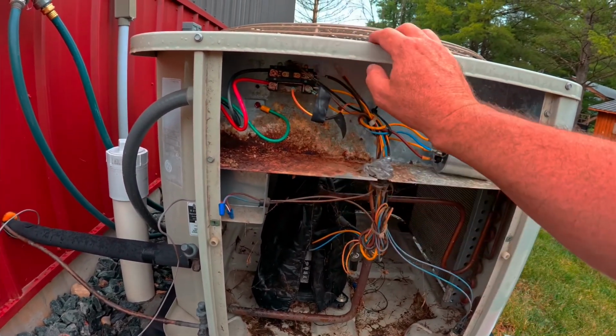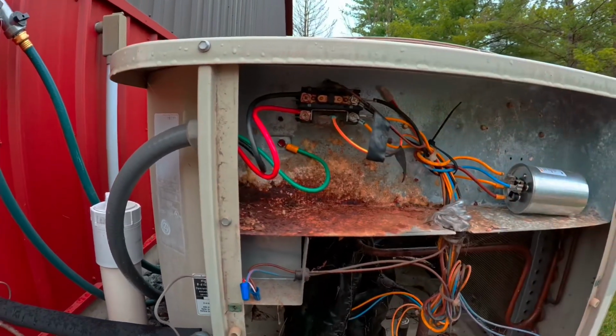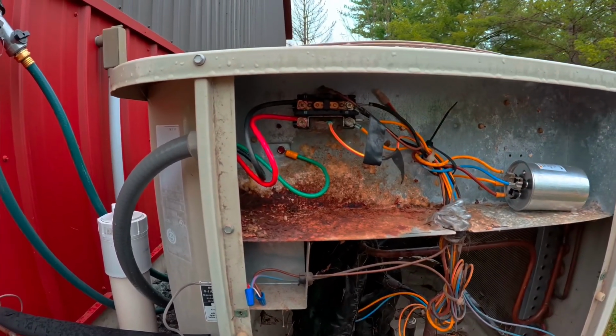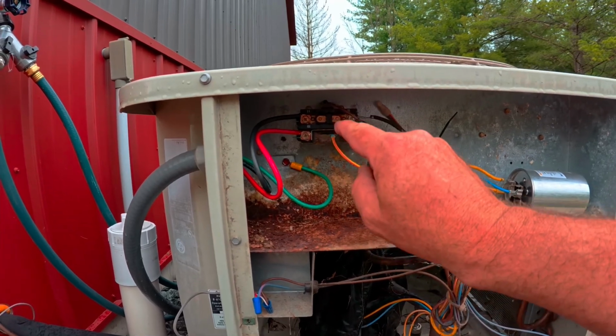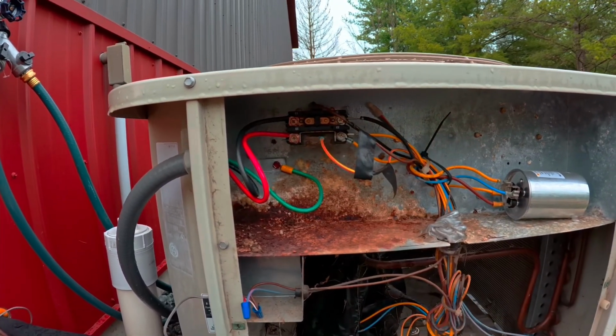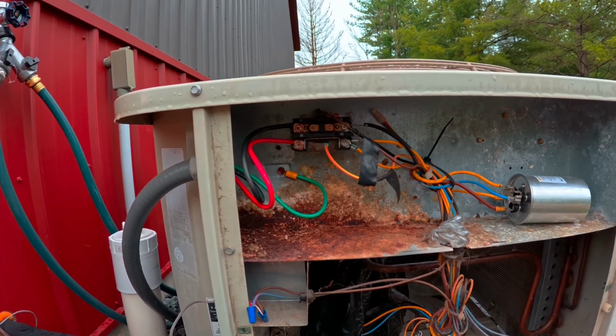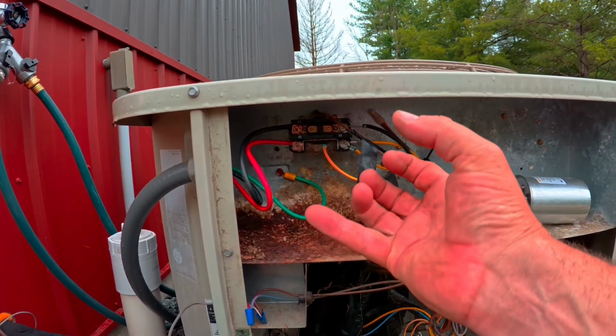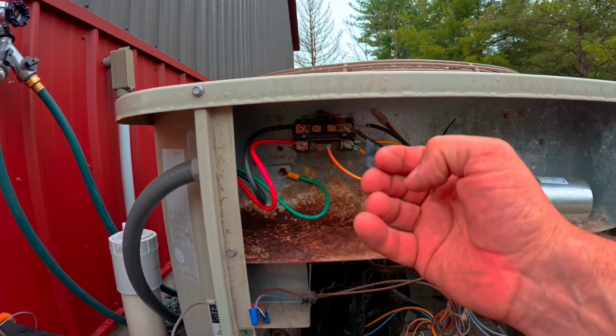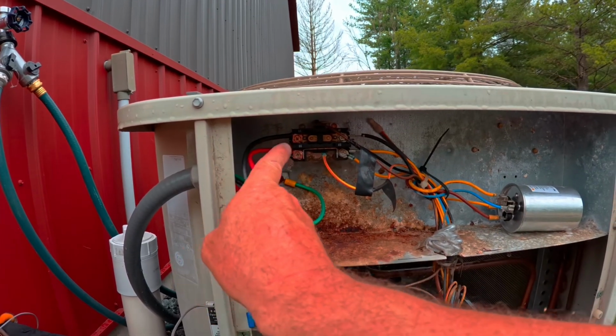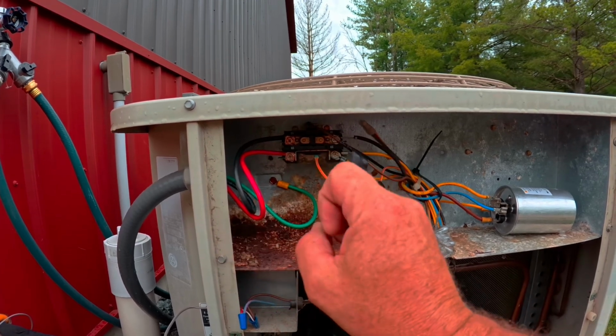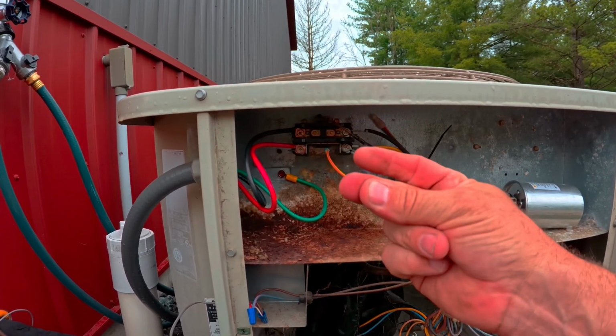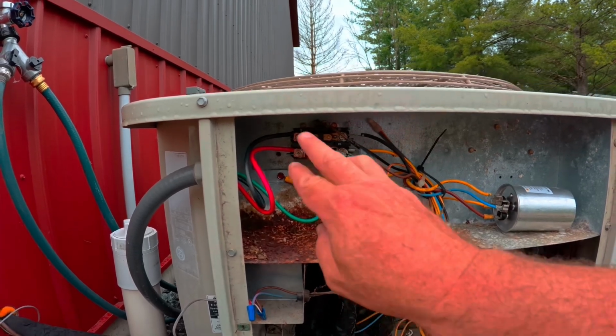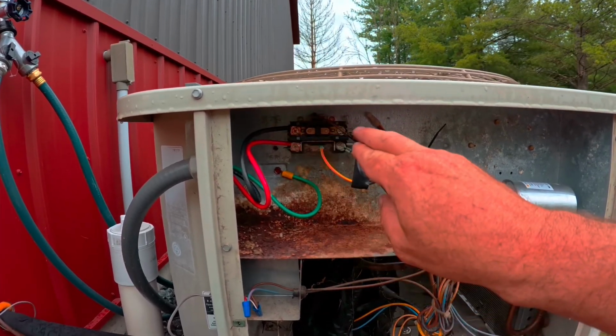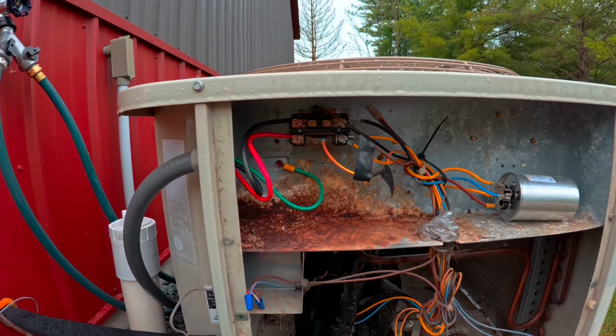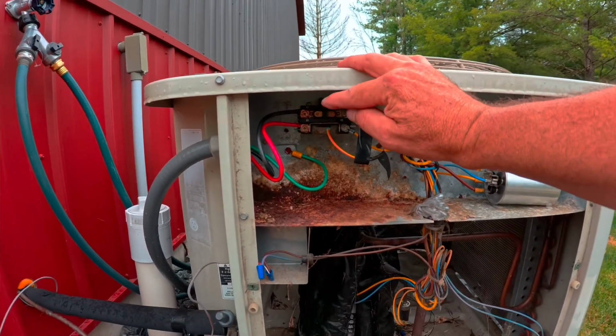Second scenario are bugs. What happens is, especially around the Midwest here with our box elder bugs, they are attracted to the heat and the vibration of that contactor buzzing when the machine is actually running. So they'll basically hoard up around that thing, and what happens is it'll shut off, and then somebody gets curious and they crawl through into the contactor, and then the air conditioning calls, slams that contactor shut, pinches that dude between the contact points, and does not allow the power to transfer across the contact to actually turn the machine on. So by doing a visual inspection, you'll see it plain as day.